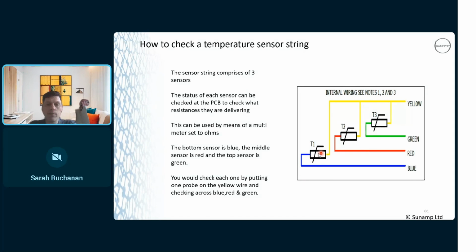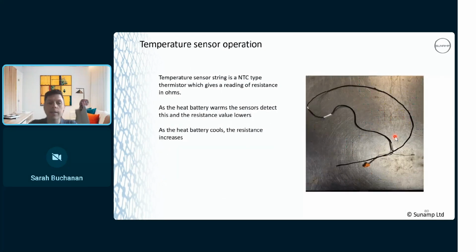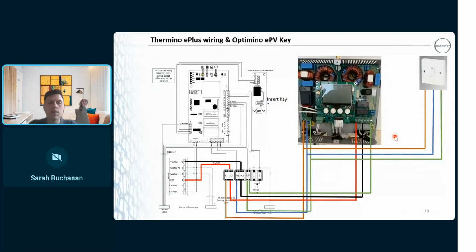So you've got T1, T2, T3. That's your bottom, your middle, and your top sensor. So how to check them? Set your multimeter to resistance, and using the yellow sensor wire as a common, you check across yellow to blue, yellow to red, yellow to green. If you see up here, that's your sensor wire connections. So with yellow, blue's your bottom, red's your middle, and green's your top.